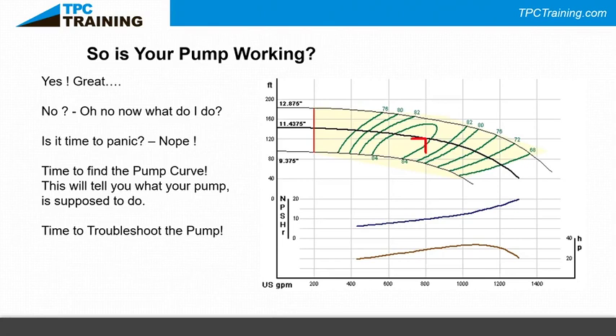Once you start choking off discharge flow below 200 gallons per minute — past that red line — the pump actually stops moving liquid and begins heating it up instead. On the curve you can see the green lines and the reliability percentage markers. As long as the pump operates within that red reliability percentage band it will be a good performer and probably won't give you many problems.